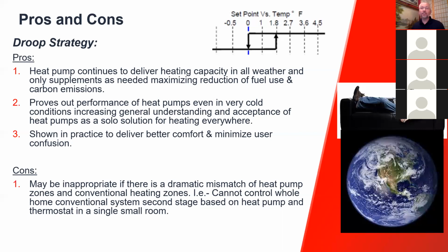Okay, this may be a circumstance where, in the course of the installation of the heat pumps, you would look at that zone, or it could be a remote distant bedroom, and you say, we're going to put in or modify the existing zones in order to provide heat to this area, and we're going to have a separate thermostat that's independent of what's going on with the integrated controls of the ductless heat pump and conventional heating system, for this particular area because of the distribution differences. Okay, that's sort of the best approach.